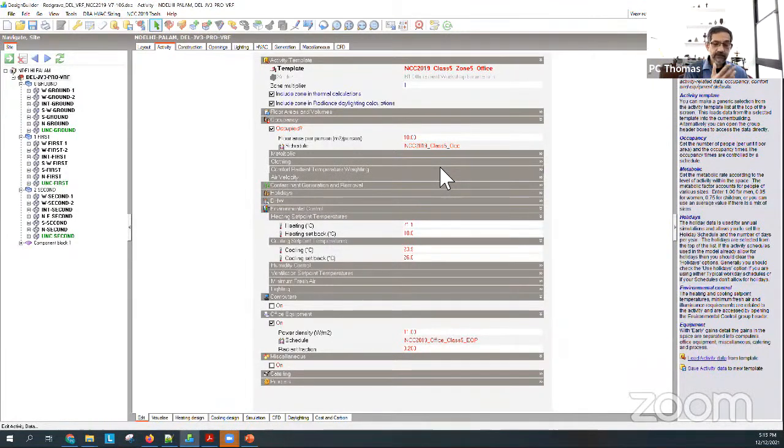Okay, that's quite generous. In Australia, in an office, we would probably say one person every 10 square meters. It might get tighter. I think in India, I've seen numbers as low as one person every 7 square meters. Now, of course, with COVID, that may change. I don't know.